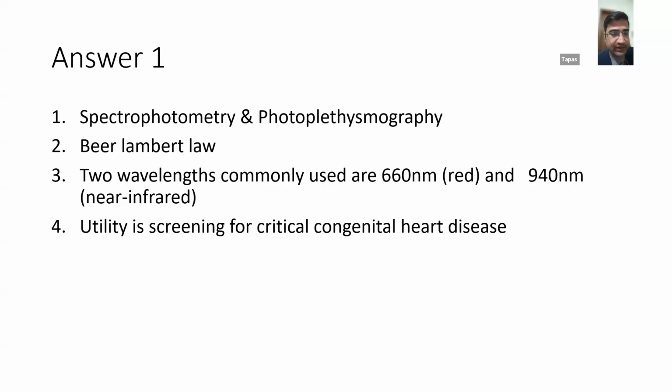And what is photoplethysmography? The pulse oximeter basically detects the oxygen saturation in the arterial blood and not in the venous blood or the capillary blood. How is it done? It measures the absorption characteristics in the pulsatile blood and excludes the measurement in the non-pulsatile blood, which is there in the venous blood and the capillary blood. So photoplethysmogram is the principle by which it measures the arterial oxygen saturation and not the venous and capillary oxygen saturation.